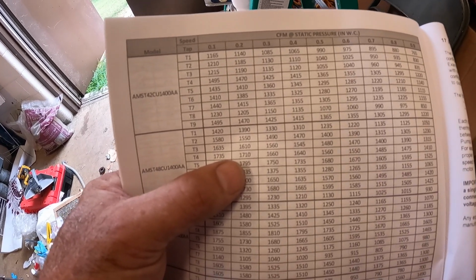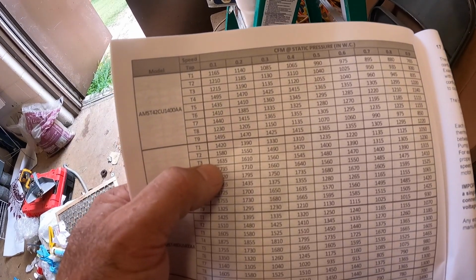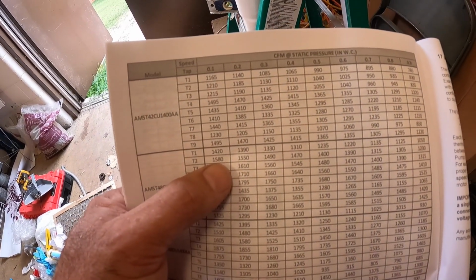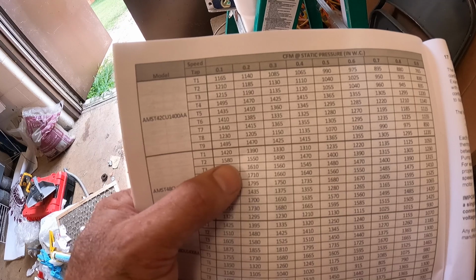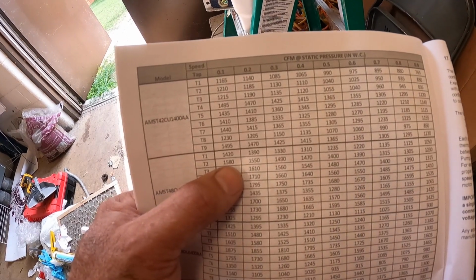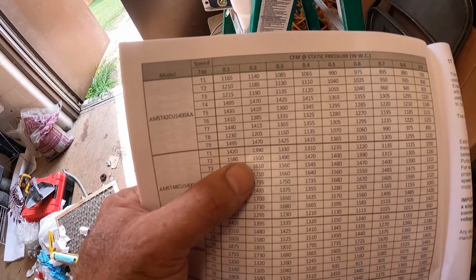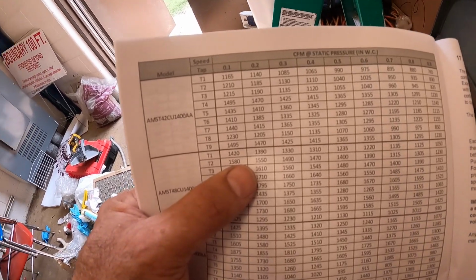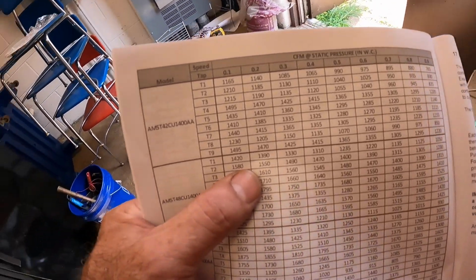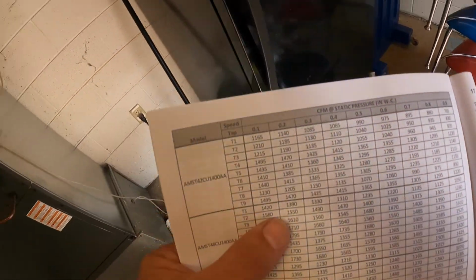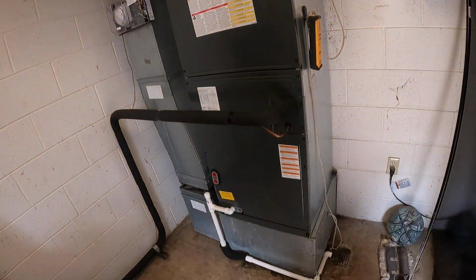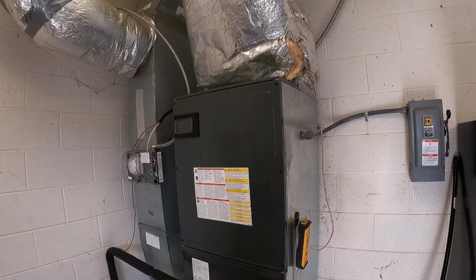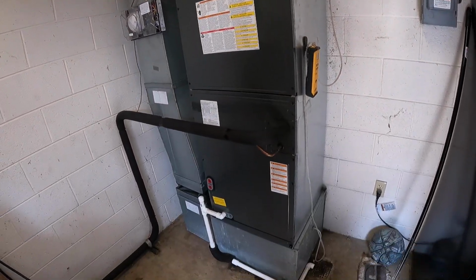I think we should probably back it off to about T-tap 3, or we could even go down to T-tap 2, because the static will probably drop a little bit. I'm going to put it on 2 and we'll recheck the static. That'll give us over 1500 CFM on a 4-ton unit. And like I say, I think they rated this unit when they did the AHRI testing at 1450, I believe is what it said.